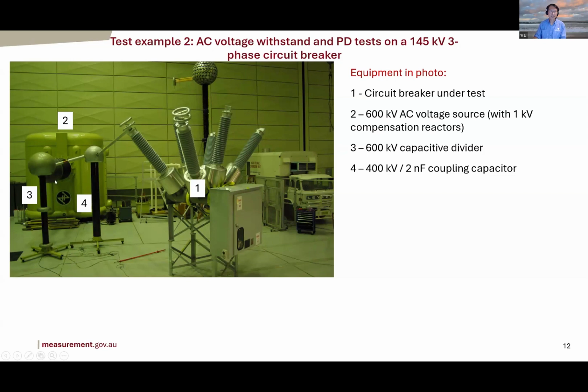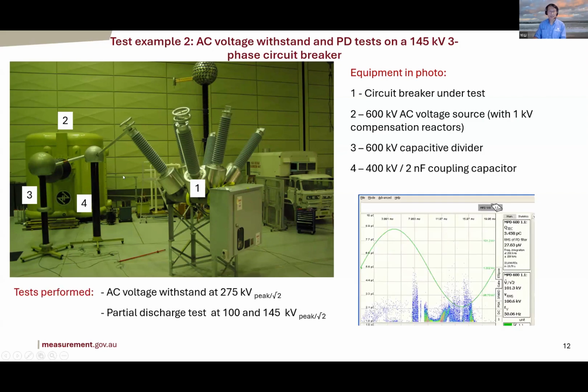In this particular test, not only the withstand, we also did the partial discharge test. So in the partial discharge test, this is the source, this is the voltage divider, connected to the low voltage meter. There's another extra device called a coupling capacitor that couples the high frequency partial discharge to the partial discharge detector. That's how you test partial discharge. This picture here just shows many small discharges. You can see that expressed in picocoulombs. The sensitivity of the PD detectors is normally a couple of picocoulombs or less.